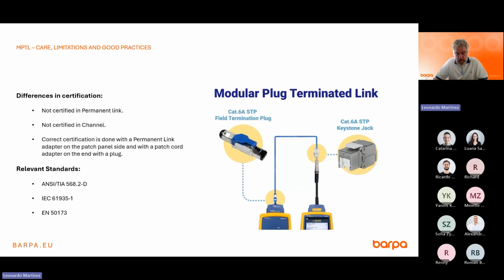One of the main problems before the MPTL definition is that there was no possibility to test correctly our link with a connector and a field terminated plug. We could use permanent link, but the problem is that the permanent link adapters are also male, which means we cannot attach it to the male field terminated plug ending.